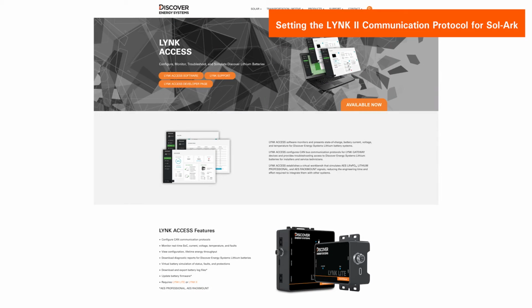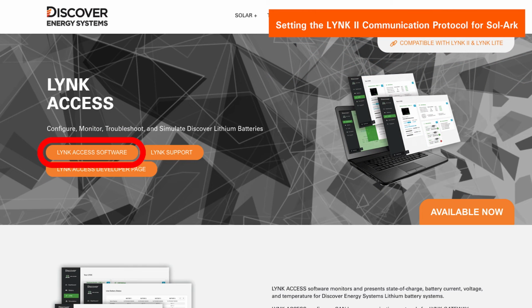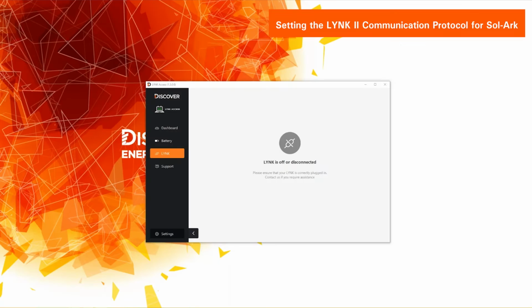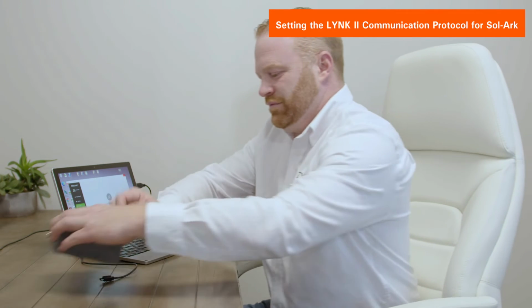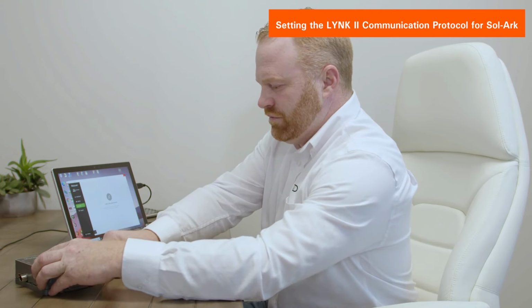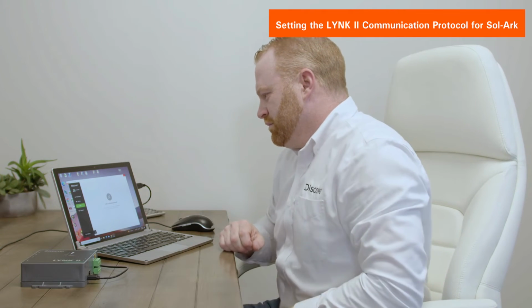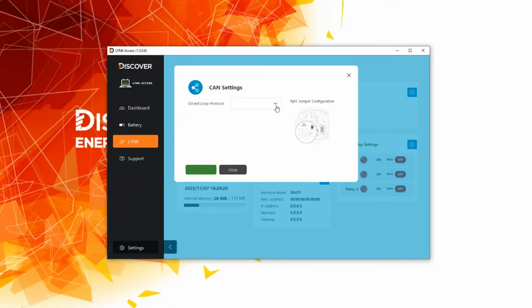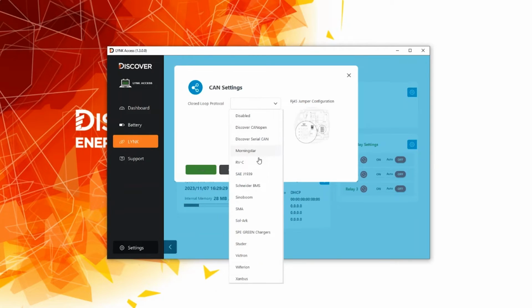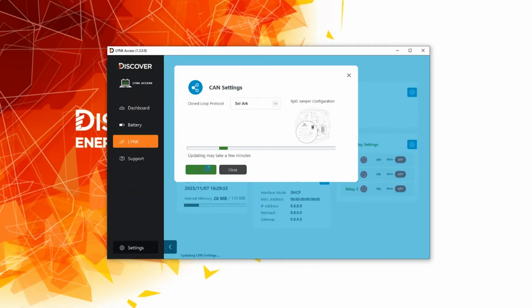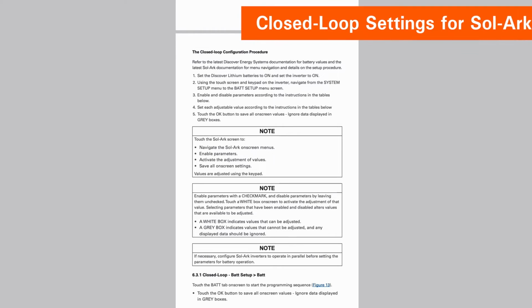To begin, download and install the LYNK Access software to a Windows-based PC from discoverlithium.com. Then, open LYNK Access, connect your PC to the LYNK II Gateway using the USB Type-B mini plug cable that comes with the LYNK Gateway. Select the Sol-Ark communication protocol using the LYNK Access software and save the setup. Now it's time to set up the closed-loop parameters.